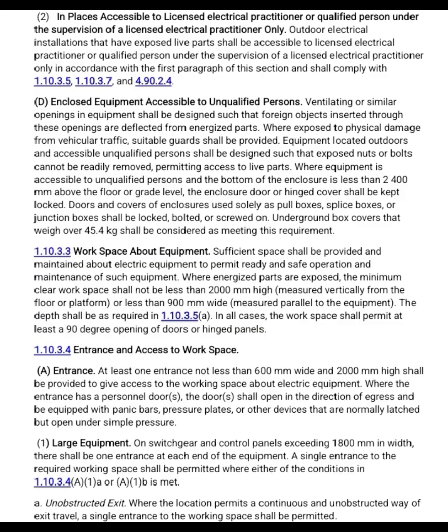Number 2. In places accessible to licensed electrical practitioners or qualified persons under the supervision of a licensed electrical practitioner only, outdoor electrical installations that have exposed live parts shall be accessible to licensed electrical practitioners or qualified persons under the supervision of a licensed electrical practitioner only. In accordance with the first paragraph of the section, they shall comply with 1.10.3.5 to 1.10.3.7 and 4.90.2.4.